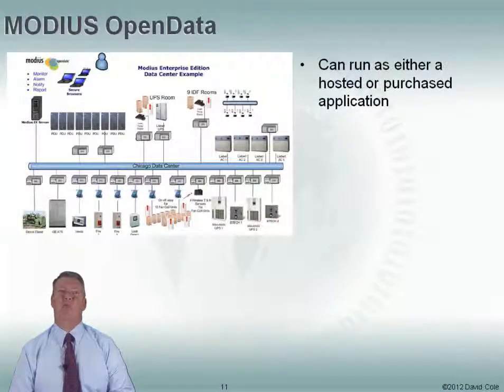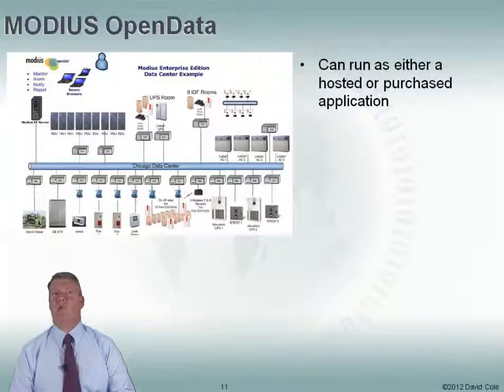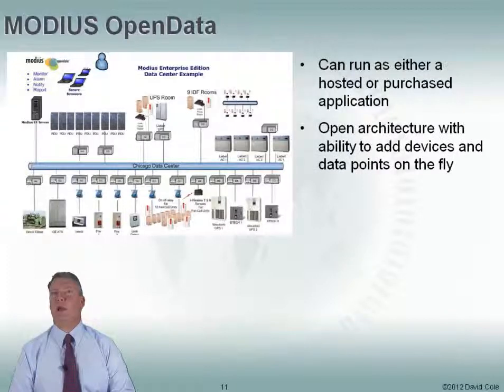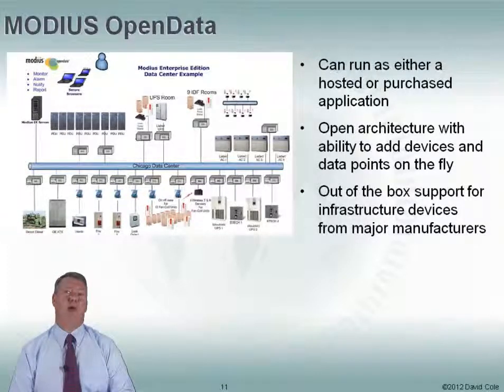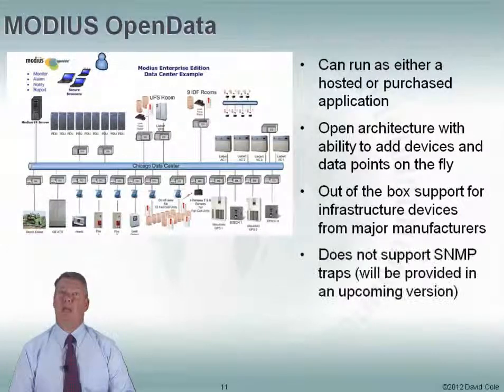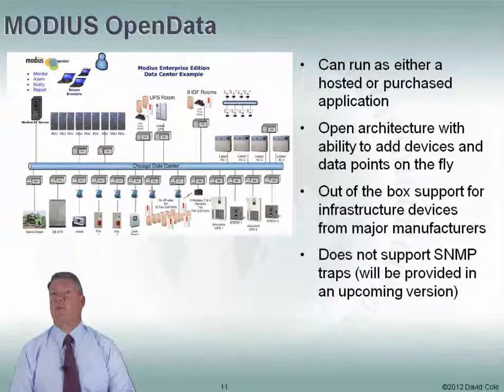Modius Open Data has a really nice backend architecture — it's a very scalable architecture. They do a lot of nice things for collecting data from various devices. They can run it as a hosted solution or as a purchased application. It's a very open architecture, so you have the ability to add devices and data points on the fly — probably a better job of that than anybody on the market. They do have out-of-the-box support for a lot of infrastructure devices from major manufacturers, but you can also add your own. It doesn't currently support SNMP traps, but that is going to be provided in an upcoming release.